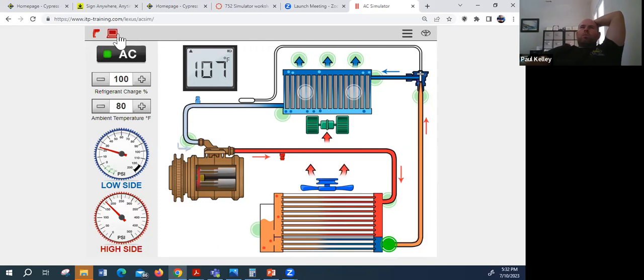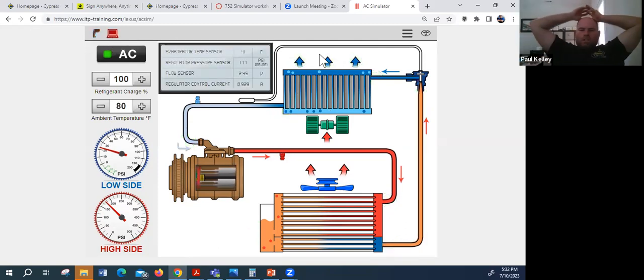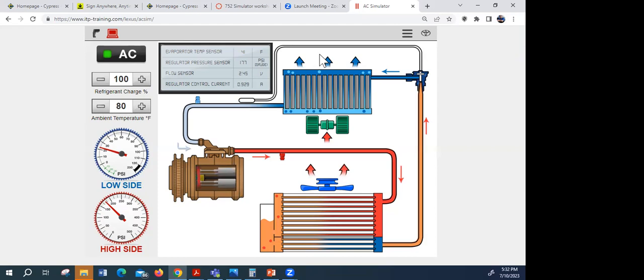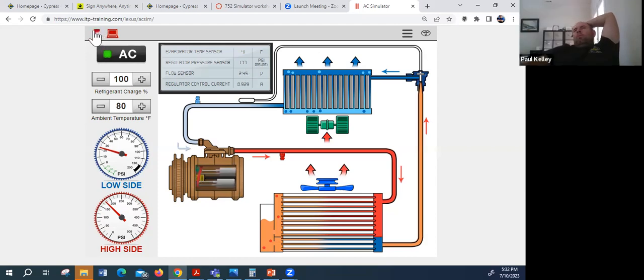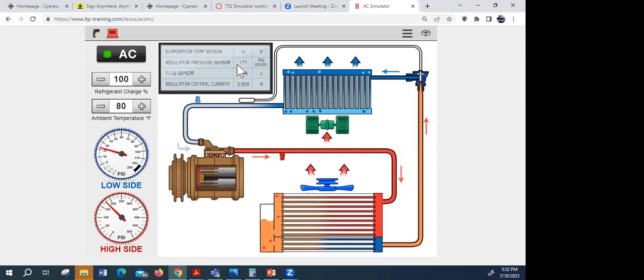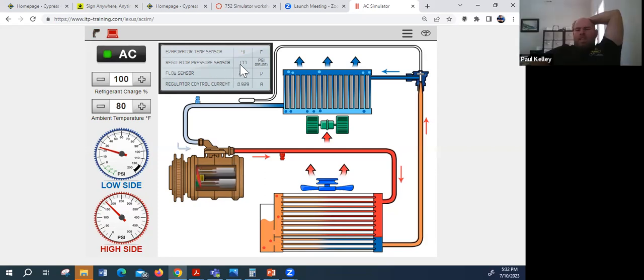The other thing you can do is get the tech stream out and see a few things, like what the evaporator temperature sensor is reading. So if the evaporator temperature sensor is 41, do you think the sensor is good or bad? It's good, it's reading normally. How do you know? Because you just check with the gun and it's reading around the same. Exactly, that's exactly how you test that sensor.